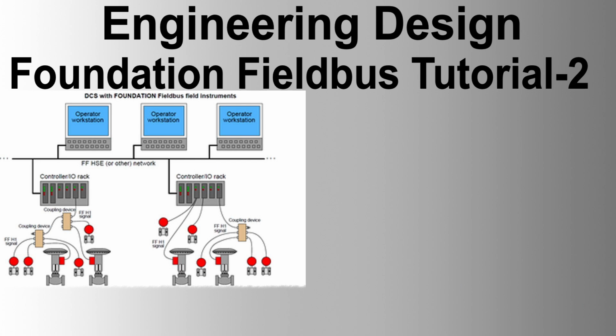Scaling and square root calculation. L-type parameter controls scaling and square root. PV, process value, is determined by L-type. XD scale provides 0% and 100% value of channel value in its engineering unit. Outscale provides 0% and 100% value of the output value.